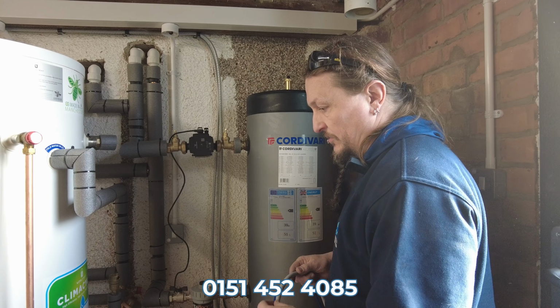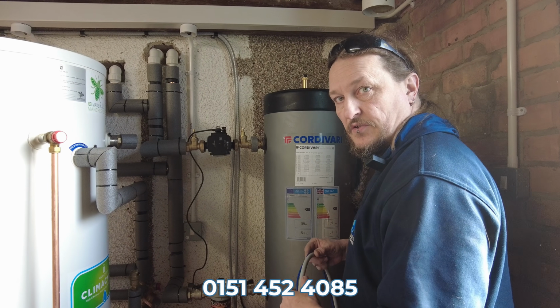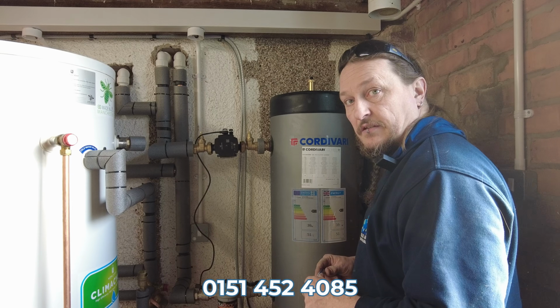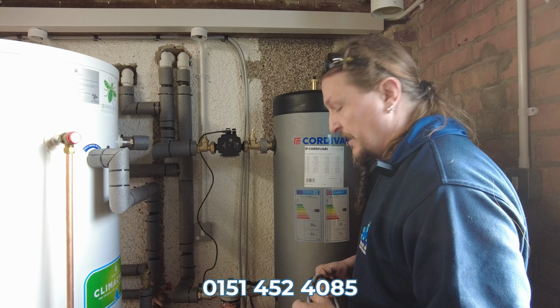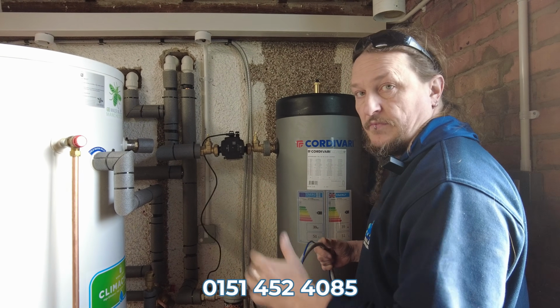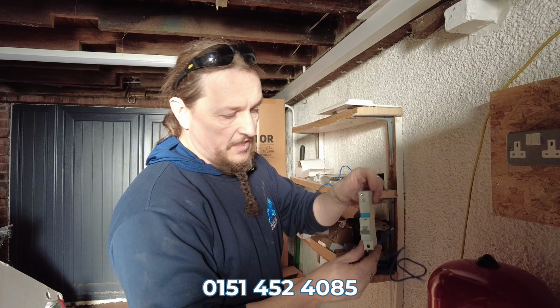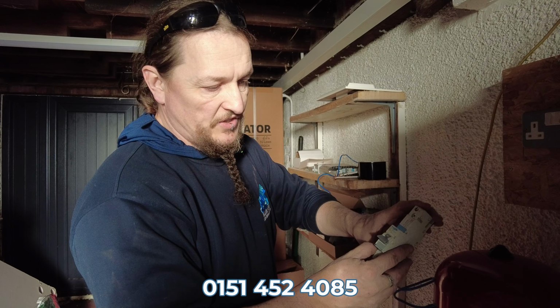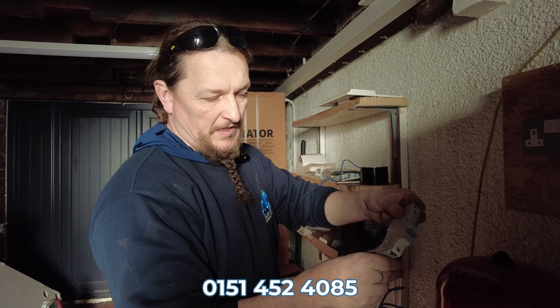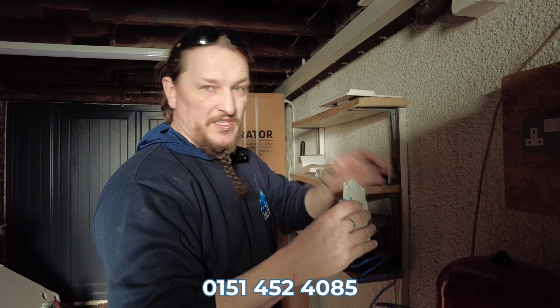So we're here on day 2, the heat pump's installed, the plumbing's installed, and today we're going to do the electric. It's going to connect up the pumps, the valves, the thermostat, all the different equipment that's needed to control it. This is an RCBO. It's a mixture of a circuit breaker and an RCD, so it measures if you use too much current, and it also measures if the current leaks to earth or isn't returning basically back through the neutral where it's supposed to be, so it's a lot safer.